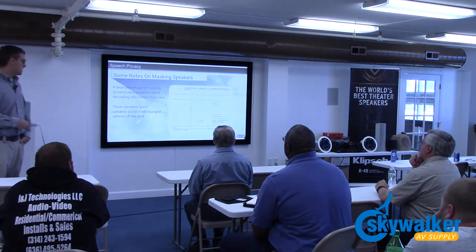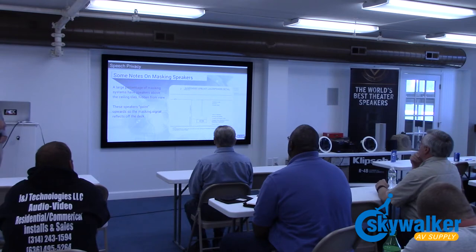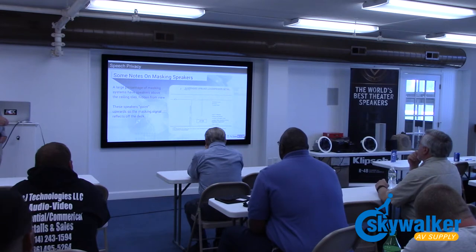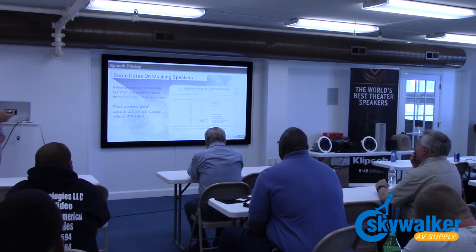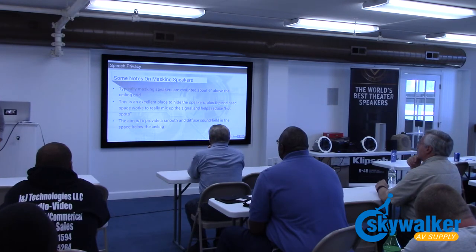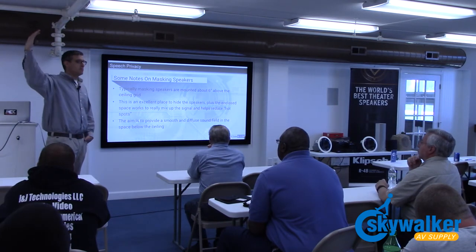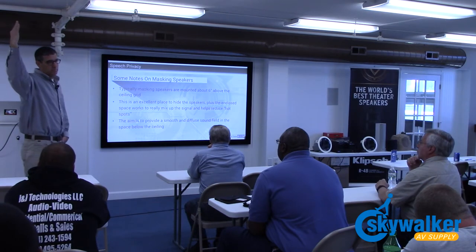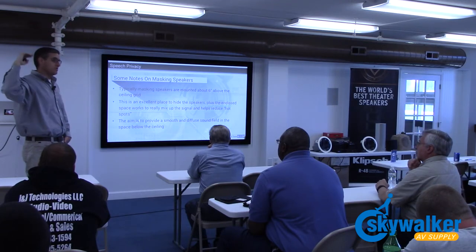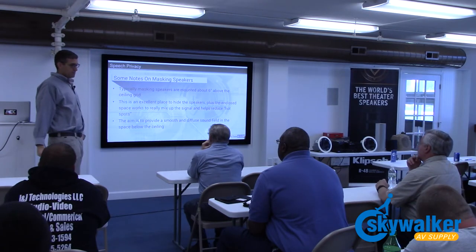All right, so this is my sound masking speaker. This is the M1000, and it's firing up in this drop-down ceiling. The sound is going to come out of this and flow over with its neighbor, and the sound's all just going to come through the drop tile. So you put them 6 inches above the ceiling tile. If you've got the 10-foot drop tile ceiling, and then there's another 10 feet above that going to the deck, you've got to get some long chain, right? Because you don't want to hang it all the way up by the ceiling, because then all that sound's got to come way down, and you're going to have to really tap that speaker in order to make it loud enough to be heard by the time it gets down to the listener. So you put it about 6 inches above the ceiling tile.